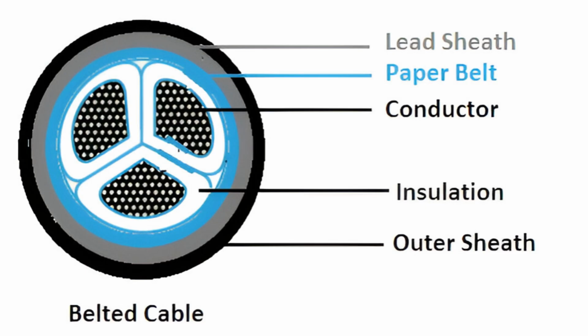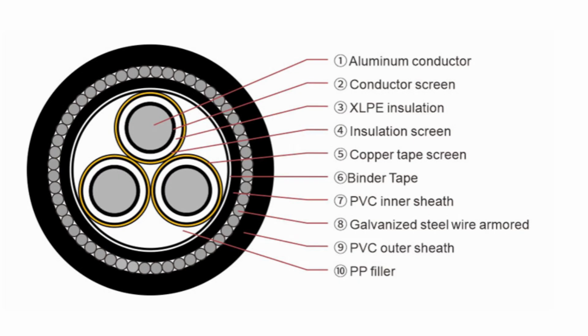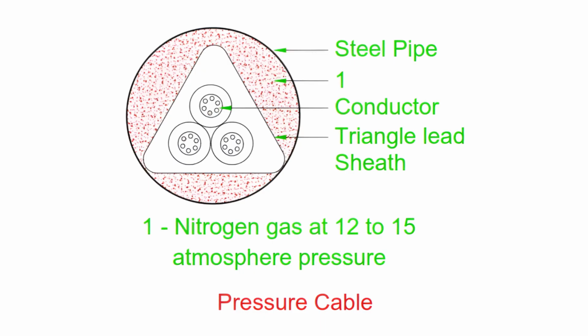Belted cables are used up to 11 kilovolts, sometimes extended to 22 kilovolts. They have paper insulation between cores and an outer lead sheath. Pretty simple and reliable, but not for high voltages, because stress builds up. Screened cables are used from 22 kilovolts to 66 kilovolts. They control leakage currents by using metallic screens like aluminum foil or woven copper belts. Pressure cables, on the other hand, are used beyond 66 kilovolts because they prevent breakdown caused by air voids using oil or gas pressure.